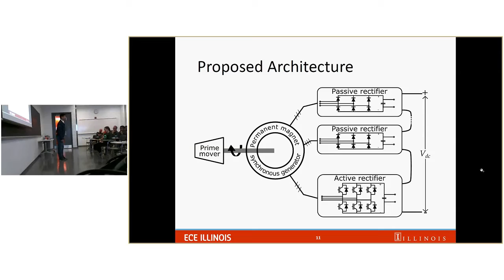So your active rectifier controls the current flowing in and out? The control algorithm is built on current control, but what it tries to regulate is this: it looks at how much voltage is generated by the passive rectifier, and it knows the value of the DC bus voltage the system needs to regulate. You take the difference, which is the voltage the active rectifier needs to provide, and the active rectifier runs a voltage control loop. But if you go deeper, the voltage control loop is actually based on D-axis and Q-axis current control. How many loops do you have in this control? Two. Current control and voltage control. Yes.